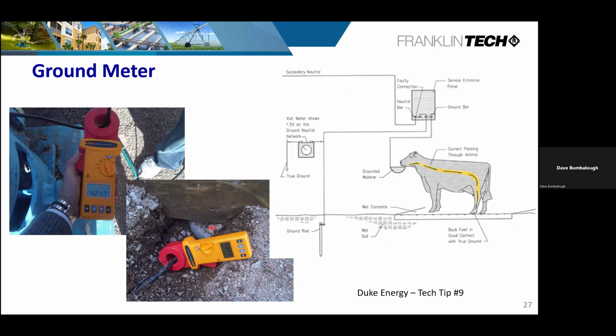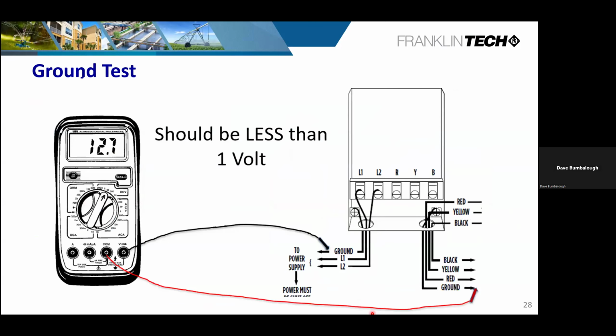This is the meter that I was talking about that I added to my toolbox. It's a ground rod meter, and it's come in quite handy. It saves the shortcuts. What I mean by shortcuts is there's another way that you can do the test, and that's at any control. You can disconnect the safety grounds with the power off, and check to see if there's any stray voltage coming in on that safety ground. If you see more than 1 volt AC, you should address it.